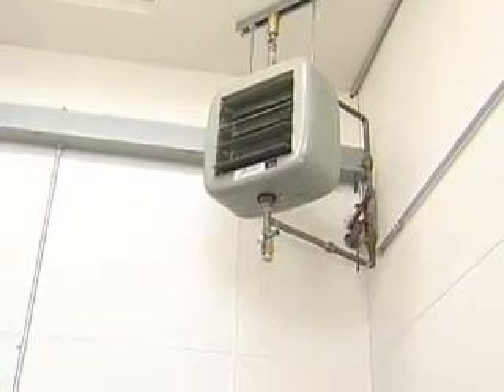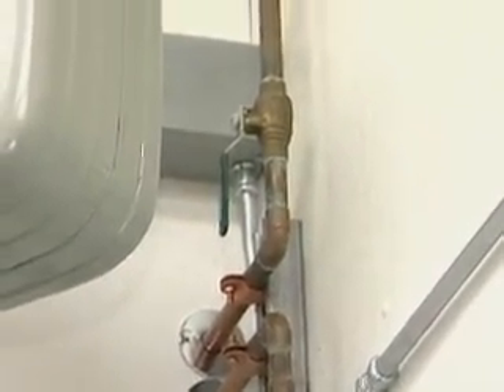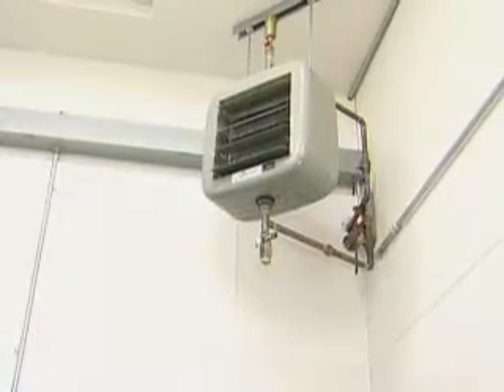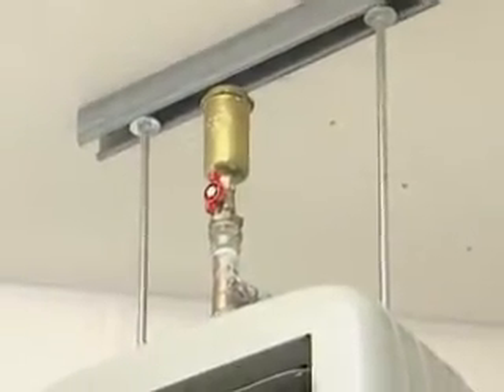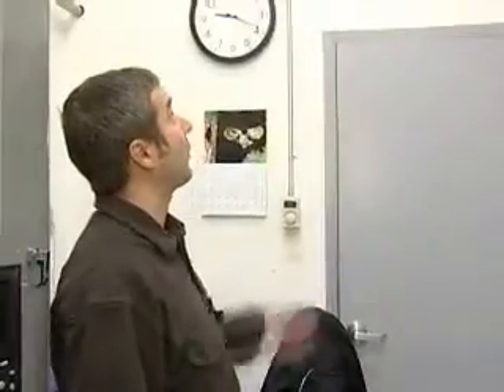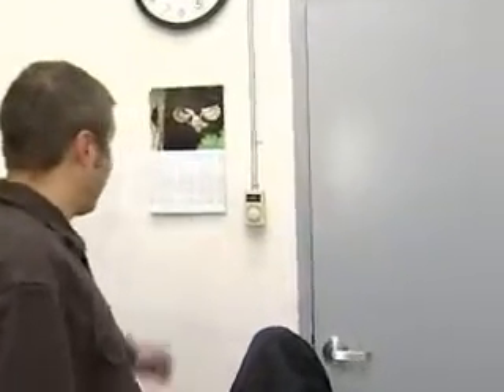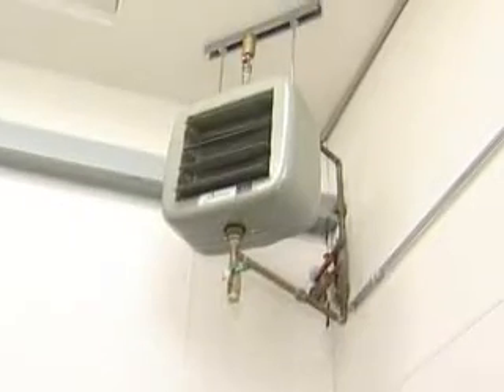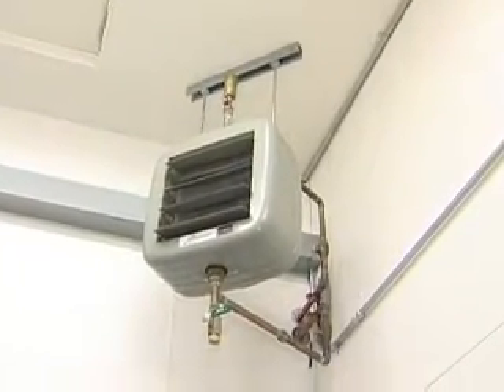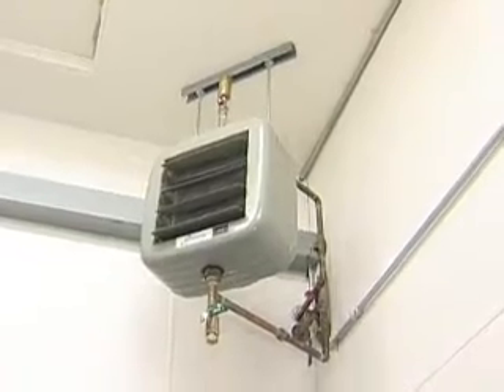Okay, in this building, the control room and the parts storage room are separated from the engine room, so they need supplemental heat. So what we have is a piping system off the heat recovery to a unit heater in each room. And just note on the unit heater, there are isolation valves where the piping comes through the wall so it can be shut off and serviced. There's a drain valve on the bottom to allow us to drain it down if we need to work on it. Then up on the top is an automatic air vent. And typically we leave these open until we get all the air bled out of the system, then we would turn it off. So that valve will need to be closed here to leave the system in service long term. The unit heater is controlled by a thermostat. When there's a call for heat, the fan will come on and it'll operate until the heating demand is satisfied.